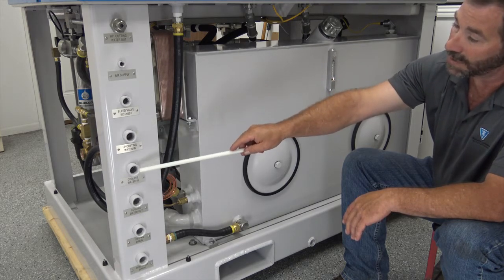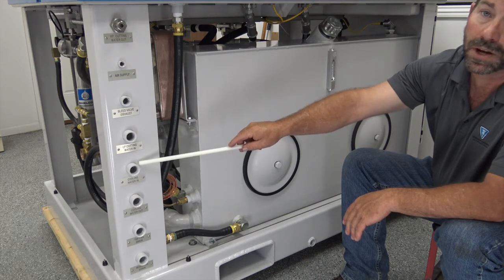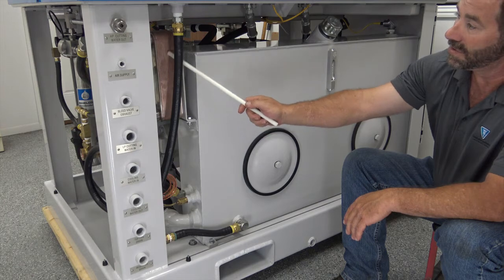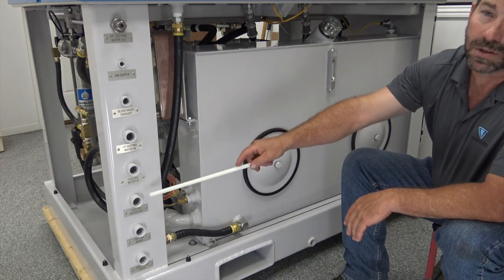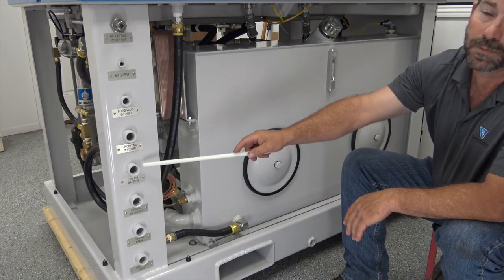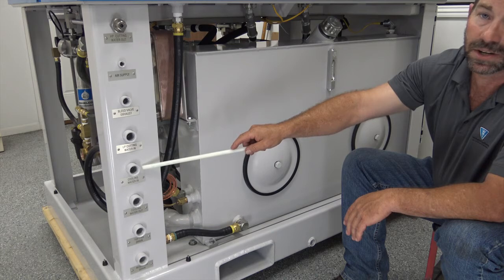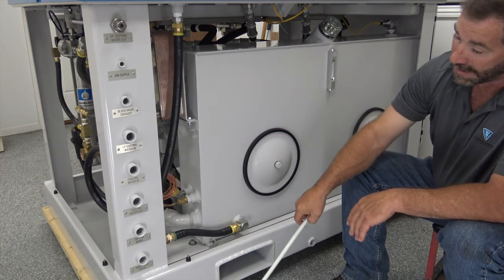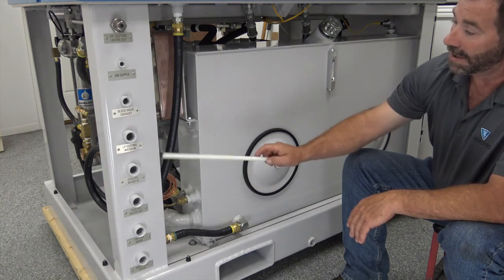Cooling water in and out, really self-explanatory. This is where your supply water would go to help cool the machine. That cooling water goes through your plate exchanger and then back out. So some people have those going to drain. Most customers find they use some kind of chiller unit and a closed circuit unit, so those are in and out for that. Top pan drain, really self-explanatory.